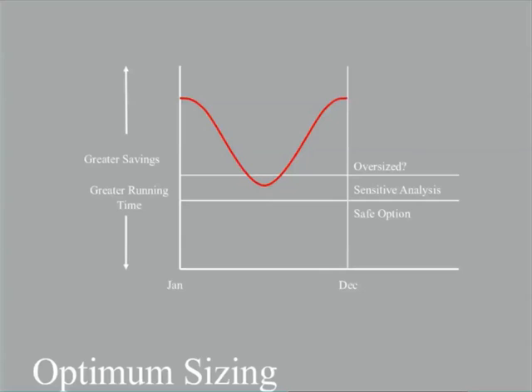But what we would always like to do is analyse as closely as we can. So perhaps understanding the thermal consumption in terms of gas consumption to the boilers, or fuel to the boilers that's providing your current heat, or if it's a site that's running electric chillers, then understanding the chiller loads and the proportion of electricity currently being used on site to generate that chilled load. Understanding all of these elements will help enable us to accurately size a unit specific to that particular project.